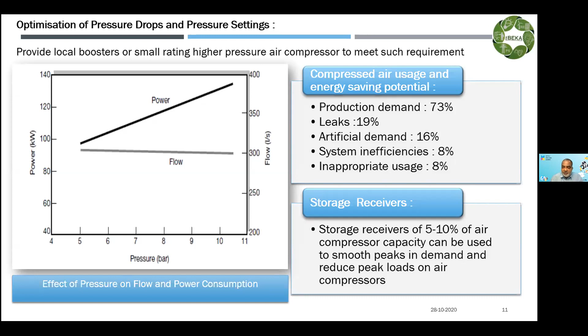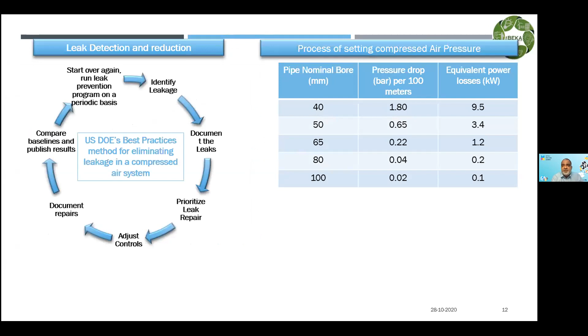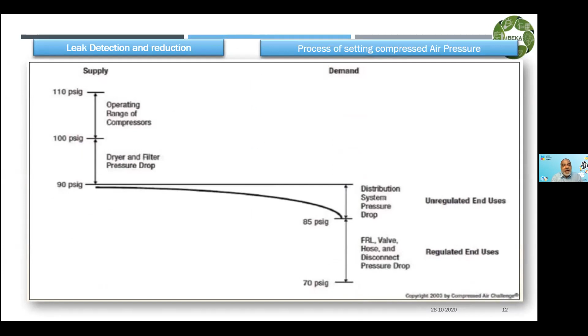And that's why in a compressor system or any system, selecting the parameter on a higher side is not a correct approach, considering energy efficiency, considering maintenance requirement, as well as considering the life of the equipment. Next comes leak detection and the process setting of the compressor, because the distribution system piping is a key. Here you will find how to set the pressure, because you are required to find the requirement, add the pressure drops, and then decide how much should be the band between load and unload setting, so that my compressor will operate with a minimal set point.